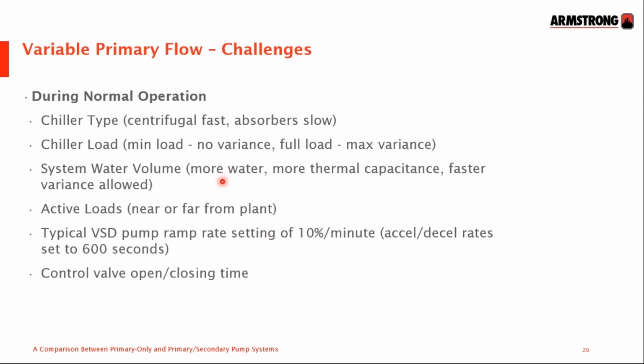So what you have to do at commissioning, in order to ensure that the chillers don't trip out on low temperature, is to make sure that the controls are slowed down. Here the pumps will have their speed controls set so that they speed up by no more than 10% a minute, so they'll start and stop over a 10-minute period. Similarly, the flow control valves on the air handling units will be set with a very large cycle time between fully open and fully shut.